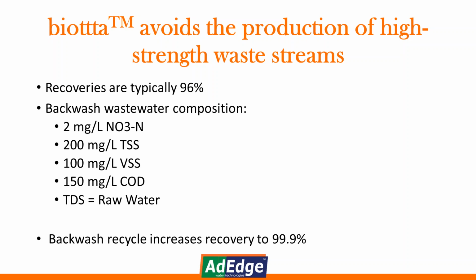Here's an example of the backwash water that comes out of our system. Recoveries are typically in that 96-97% range if you're not going to reclaim any of the water. But if you do reclaim that water, you can get up to 99.9% of that water use done. You will end up with some biosolids that will need to be managed at the end.